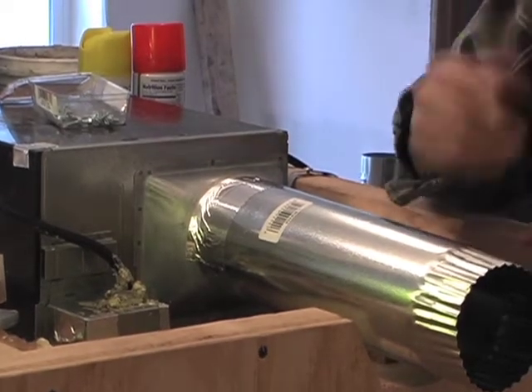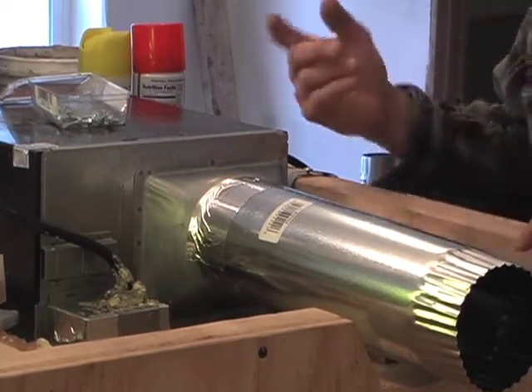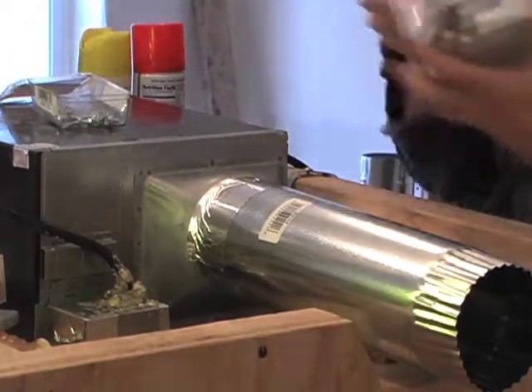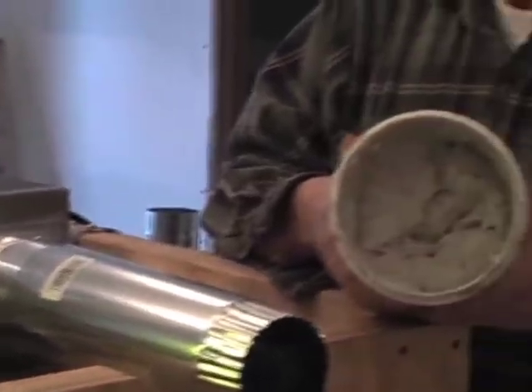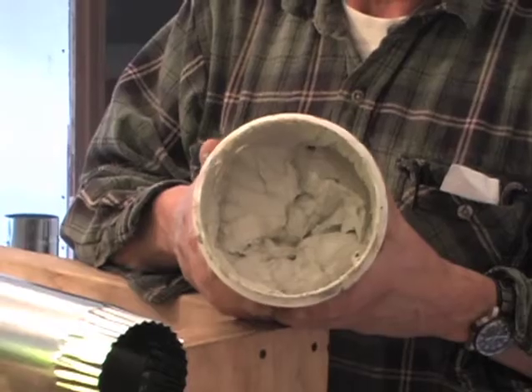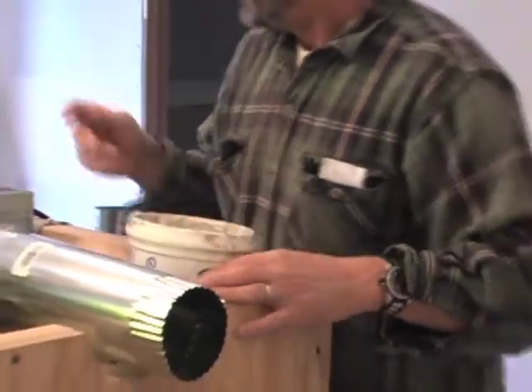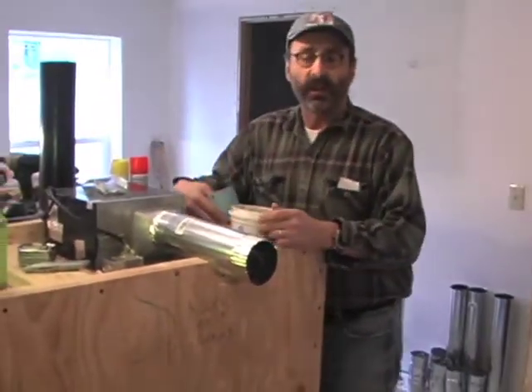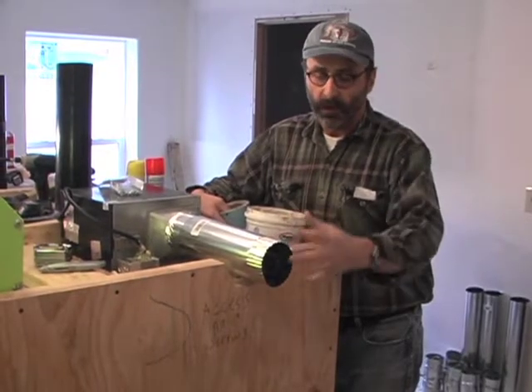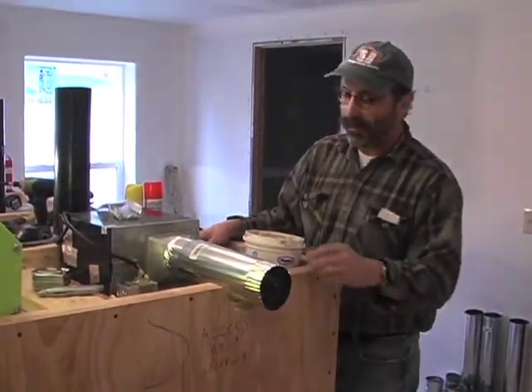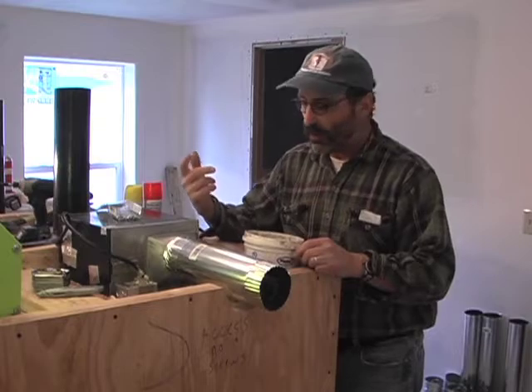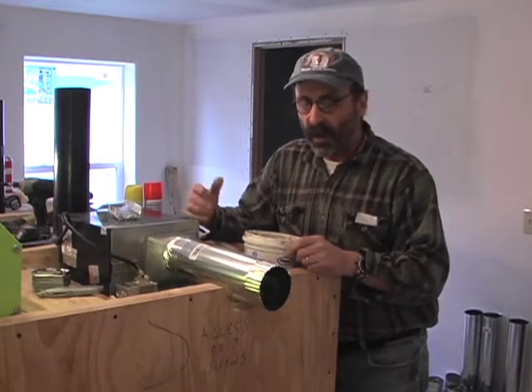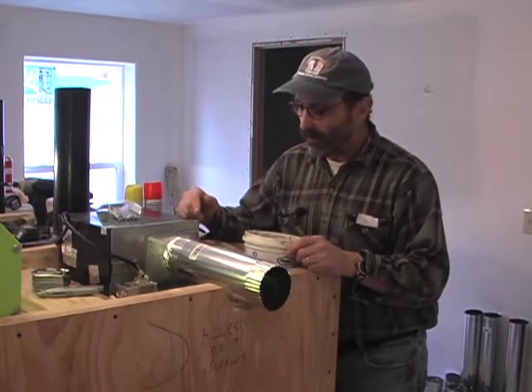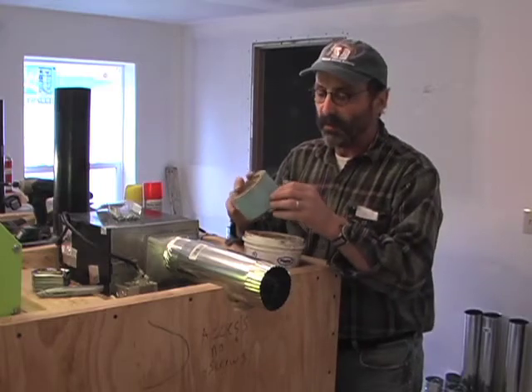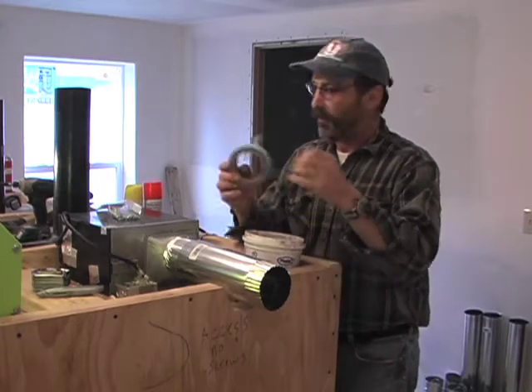Longitudinal seams are another place where we need to do air sealing. Again, it can be done with latex-based mastic, preferably never a solvent-based one. The latex-based mastic can seal up to a 1/4 inch void, depending on where the fittings are coming together. So this will seal on its own. If you do run across a defect greater than a 1/4 inch, use fiber mesh tape. So the fiber mesh tape would come on.